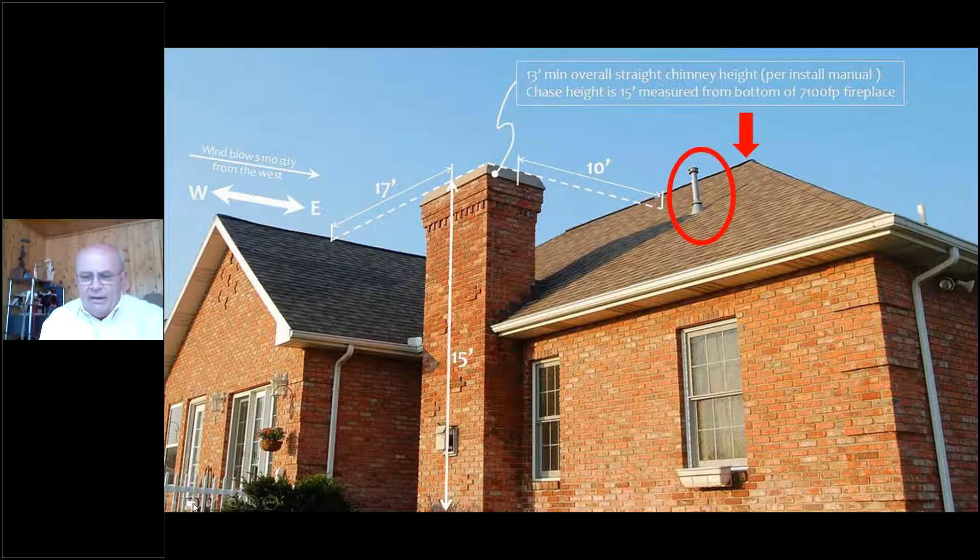This is what we call stack effect. You can also see a gas appliance venting out the roof in the metal vent pipe inside the red circle, and that vent is below the height requirements. Gas calls for a 10-3-2 rule, but if it's naturally vented, we could still have issues. Something can meet codes or standards but may not perform — that's a key consideration. The performance of the appliance is so often going to depend on whether the venting system is working properly.